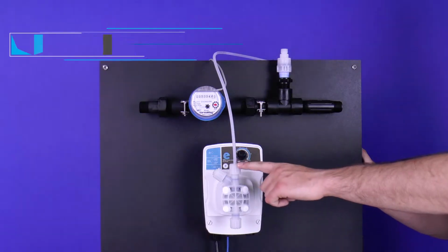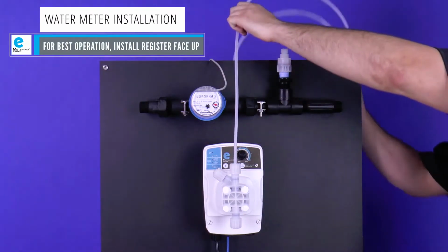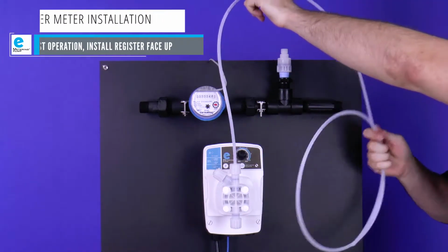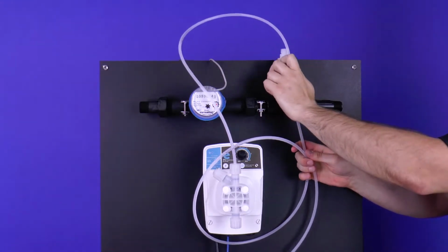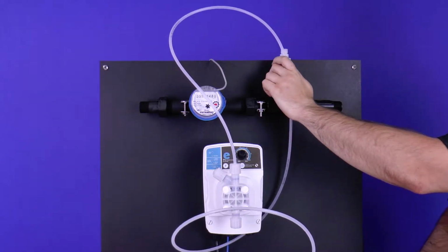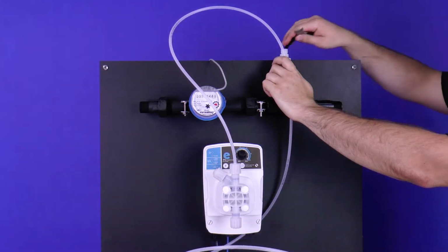Next, grab the rigid polyethylene discharge tube connected to the discharge valve. Using diagonal pliers or cutters, cut the tube so that it runs comfortably from the discharge valve to the injection valve. If the tubing is too snug, the tubing connection will come loose and produce a leak.